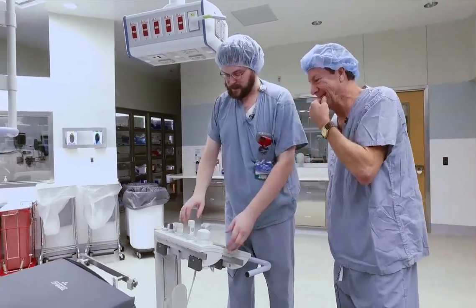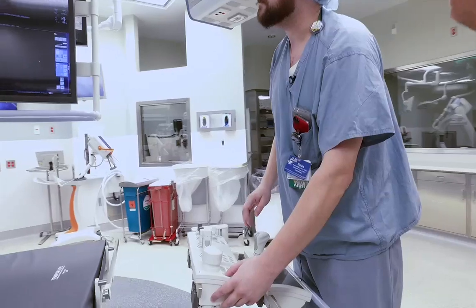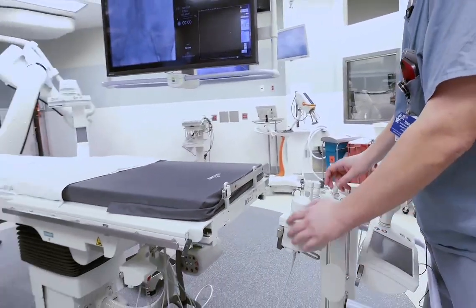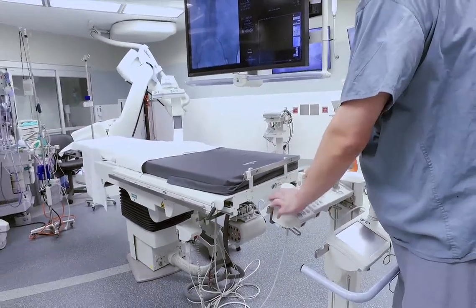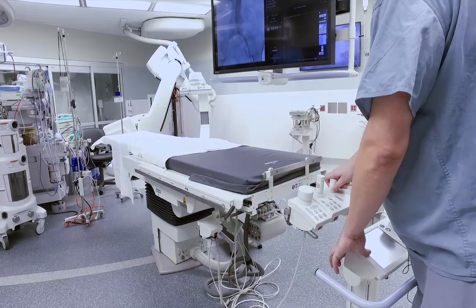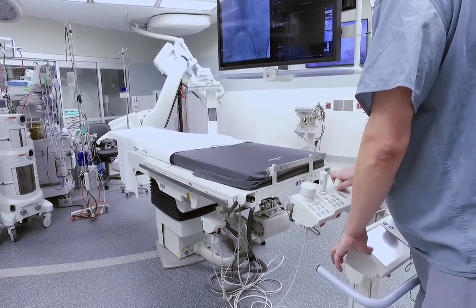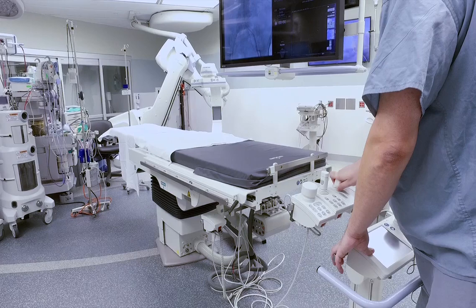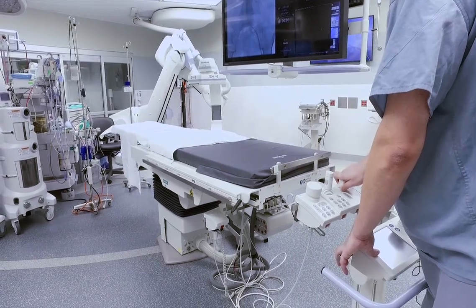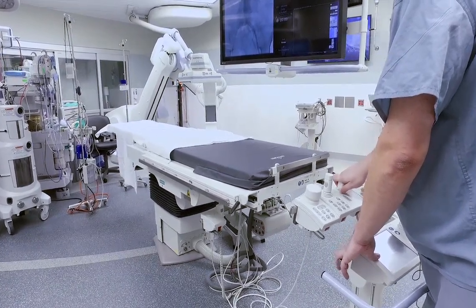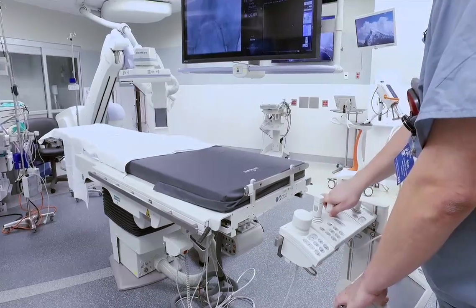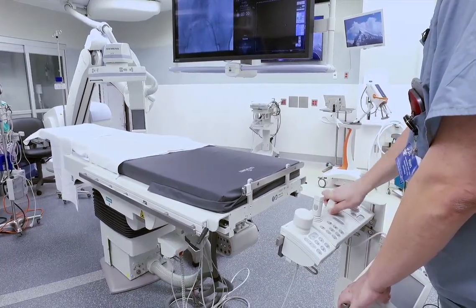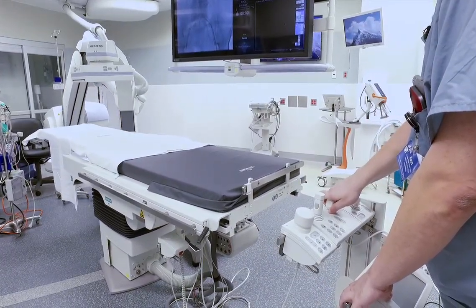Yes. So the machine's basically a traditional X-ray C-arm, which is sort of the workhorse X-ray unit in operating theaters. It's attached to a robotic arm, which is very similar to the kind you might see in a manufacturing plant. This entire equipment is also smart. So the C-arm knows where the table is and the floor and ceiling and walls. So you can't really get it to hit any of that.